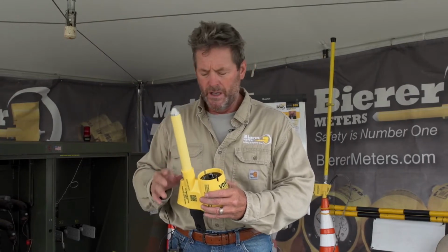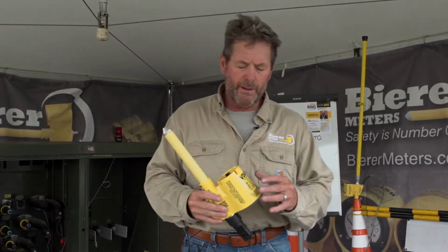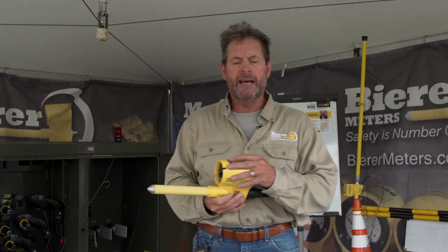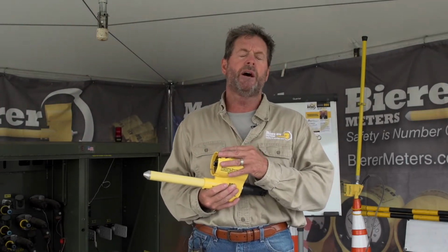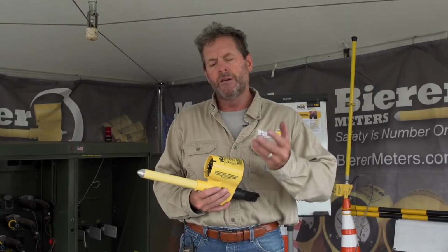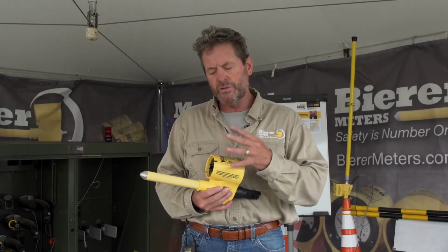That's really important. When you're using these tools, always remember that when you make contact with the conductor, the tools must be energized in order to give you a voltage indication. When you're phasing, wireless or corded, whatever, the tools must be energized.